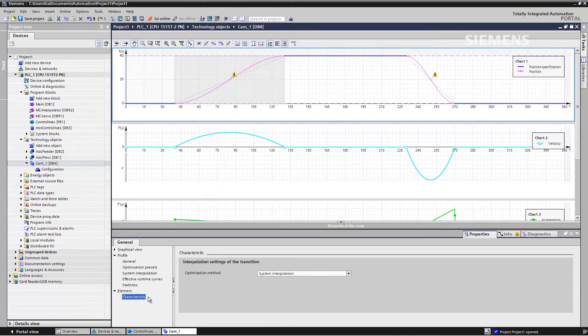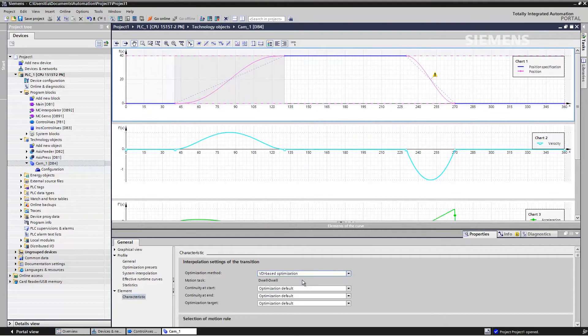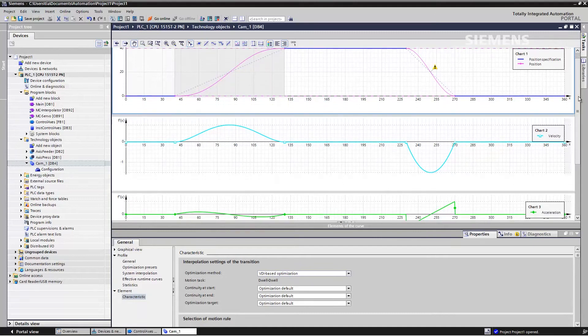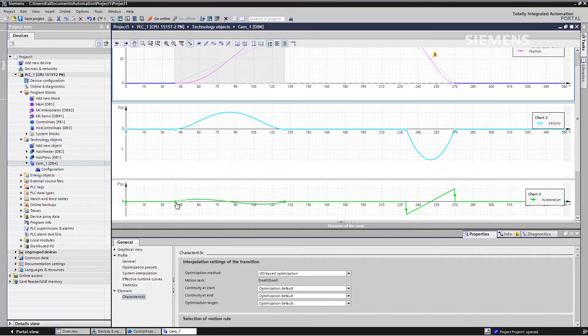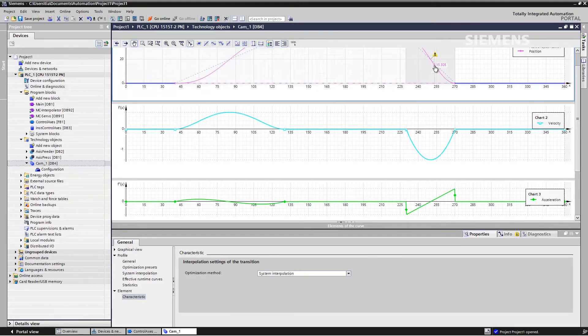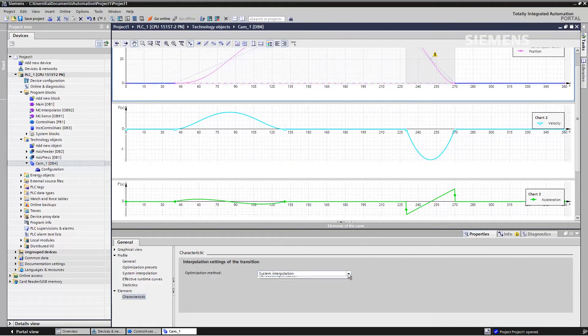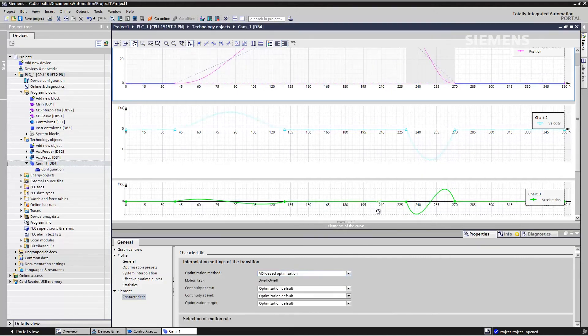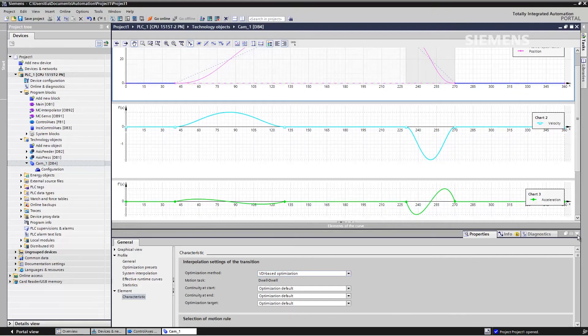To do this, we open the characteristics and switch over to the VDI-based optimization, where we can now precisely define the acceleration, speed, and jerk for this traversing movement, along with the type of interpolation. From this setting alone, we can already see that the jump in the acceleration has disappeared, resulting in a smoothly changing speed and overall a very smooth traversing movement. We apply the same method for the second transition, switching to VDI-based optimization, and we now see a smooth traversing movement.